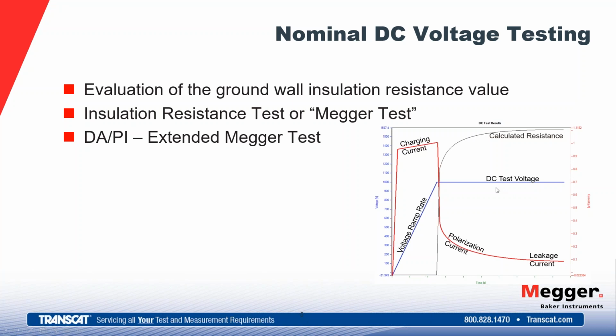Again, this voltage that we're holding at will be determined by the nameplate voltage of the motor, either at or below that. IEEE 43 speaks to recommended test voltages there, and they'll be at or below the nameplate of the motor. So as we ramp up to that voltage, basically charging current is what we're going to see mostly dominating the current that we're measuring. So we're going to allow time to pass, and as time passes, we don't change voltage. Our current at that point, what we predominantly measure, is going to be absorption current or polarization current.